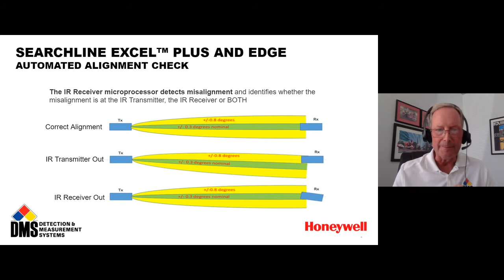I wanted to share with you all this illustration, which is basically comparing the previous Searchline Excel with the new Searchline Excel Edge. My point in this is that when you open up the box for the previous Searchline Excel that we've been supplying for a number of years, it comes in a kit form that requires assembly. So it comes with a plate, it comes with a transmitter, it comes with this mounting bracket, it comes with all the hardware that's part of the mounting bracket. All of this is disassembled, including the Allen screw there and the Allen screw there, all these various Allen screws that are loose, all of which have to be assembled along with the IR source or the IR transmitter, and then the interconnecting cable that connects the transmitter to the IR receiver. All of that has to be assembled before you can finally attach it to the post or the pole or the flat surface that you want to mount it to. And I will admit it is time consuming.